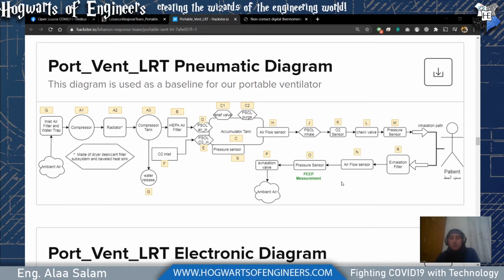And then we monitor something else. Just like we monitor the airflow on inhalation, we need to check it on the exhalation. Whatever you give in, you should receive back out, minus what the patient should have breathed. And this is what the ventilator calculates. So that's why we have VE, which is volume exhaled, and VI, volume inhaled, and VT, which is the total volume between volume inhaled and volume exhaled. The airflow sensor H we use to get VI, and the airflow sensor N we use to get VE. When we calculate VE and VI, we get the tidal volume that is measured on the circuit.